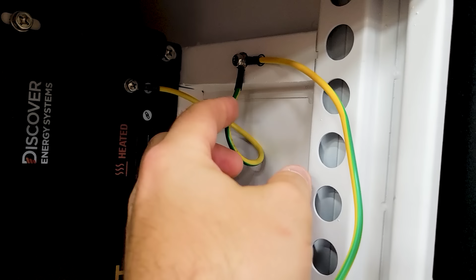All the grounding wires are now in place. Up here there are 2 on this screw because this wire came with the cabinet and it's for securing to the door. I've got all these torqued down good and tight, not to 7 Newton meters - I felt like I was going to strip out those screws - but probably to 5 Newton meters on each.